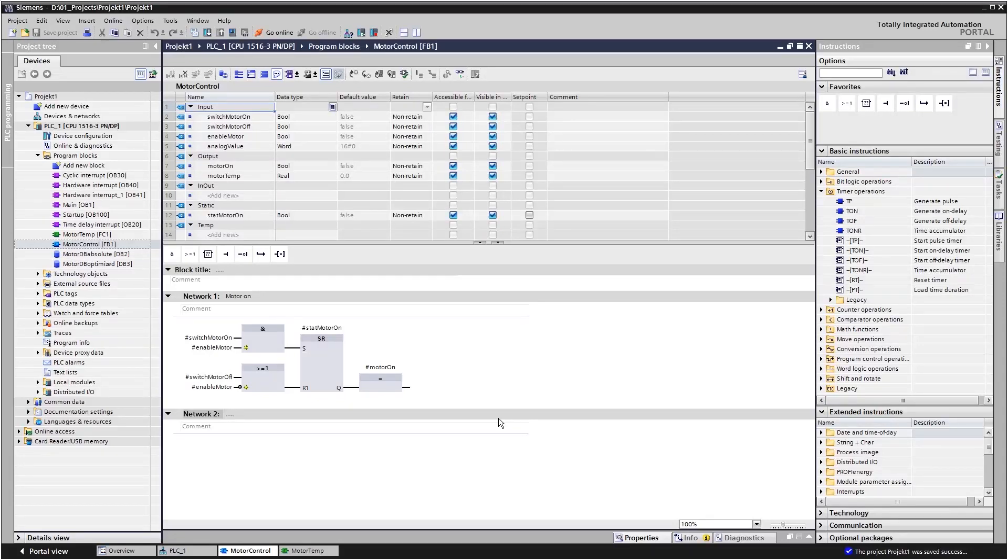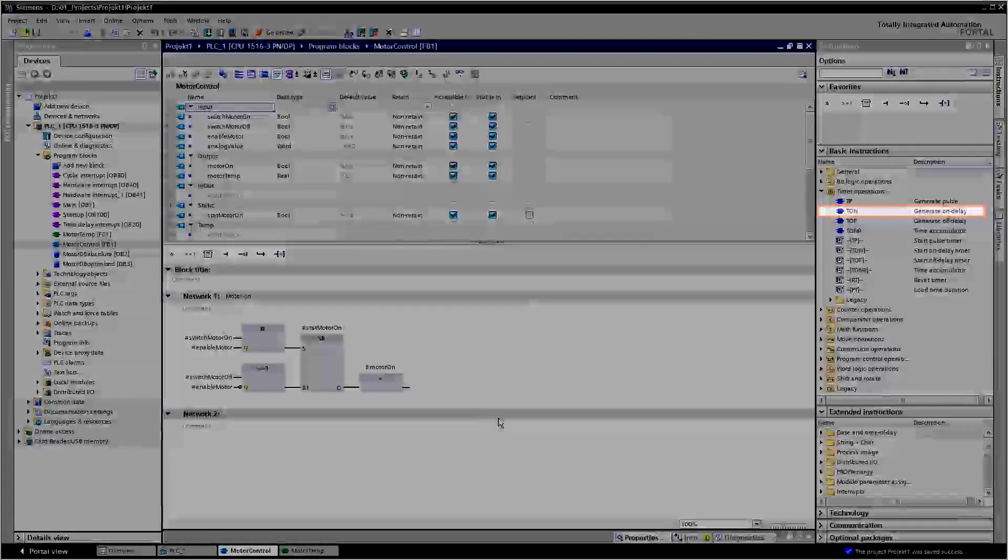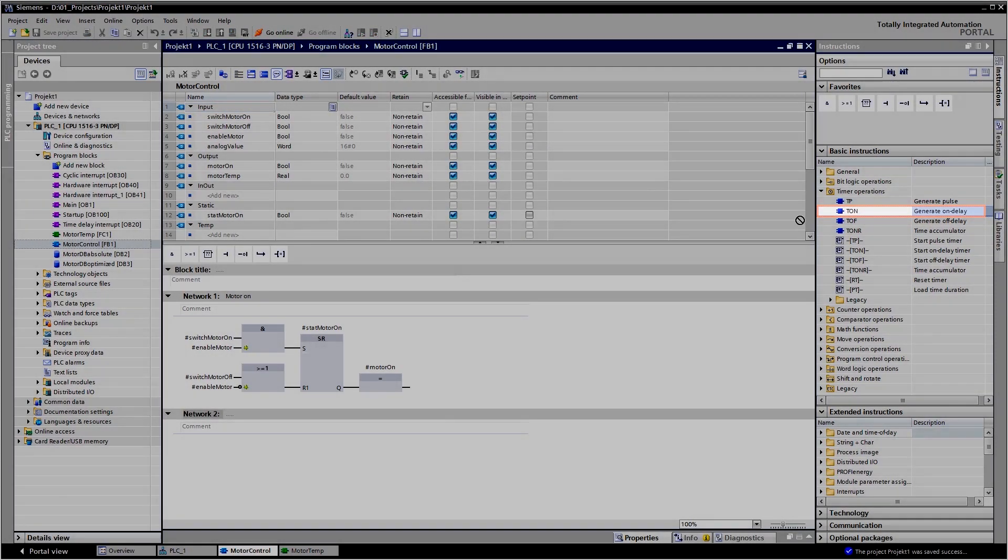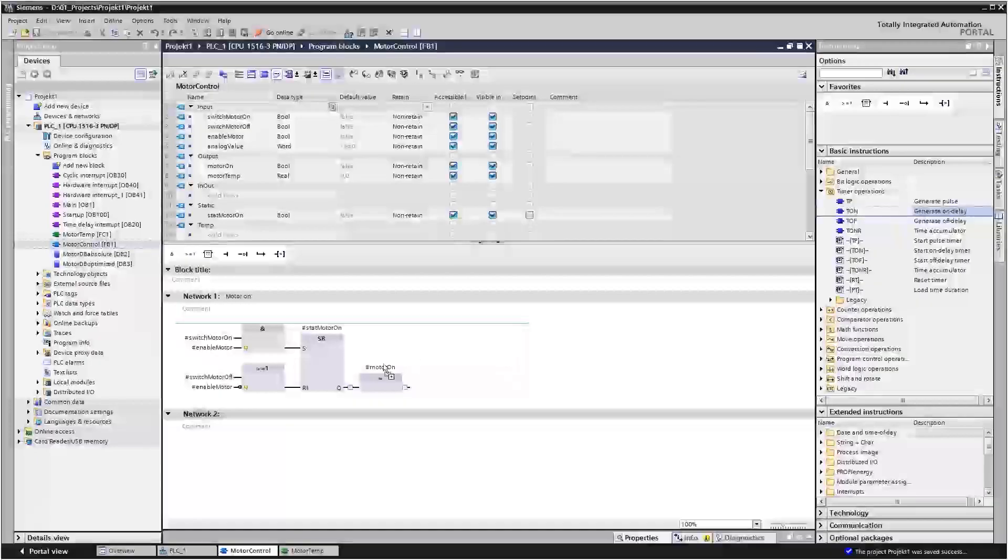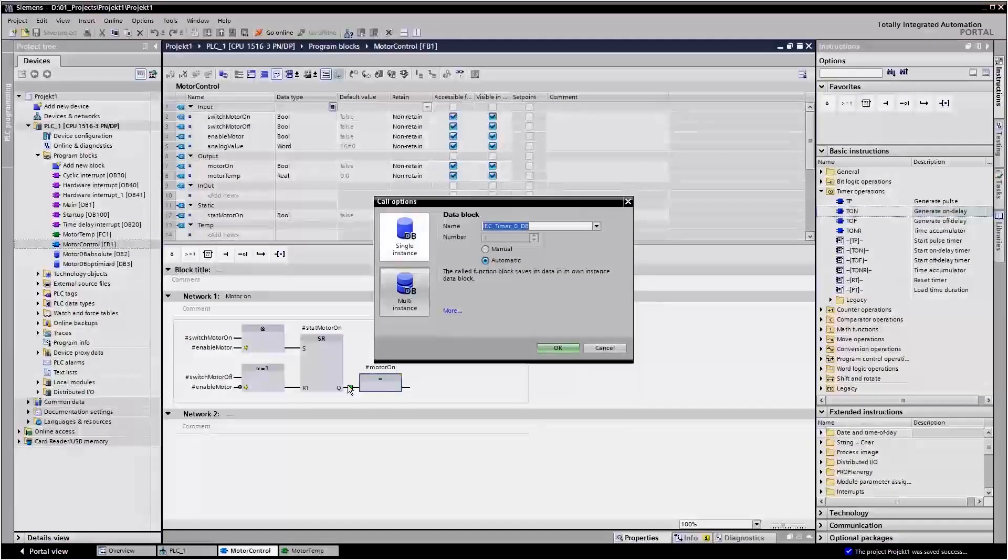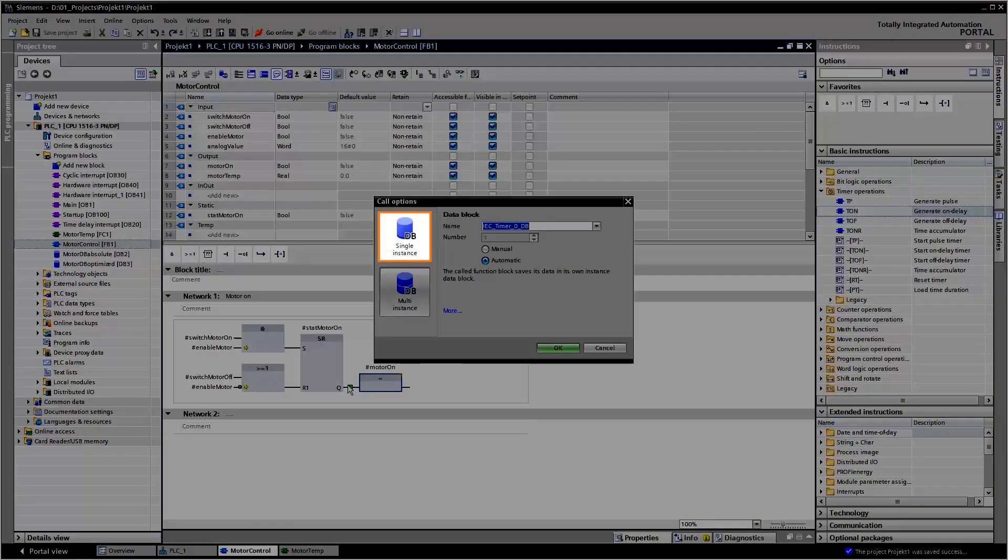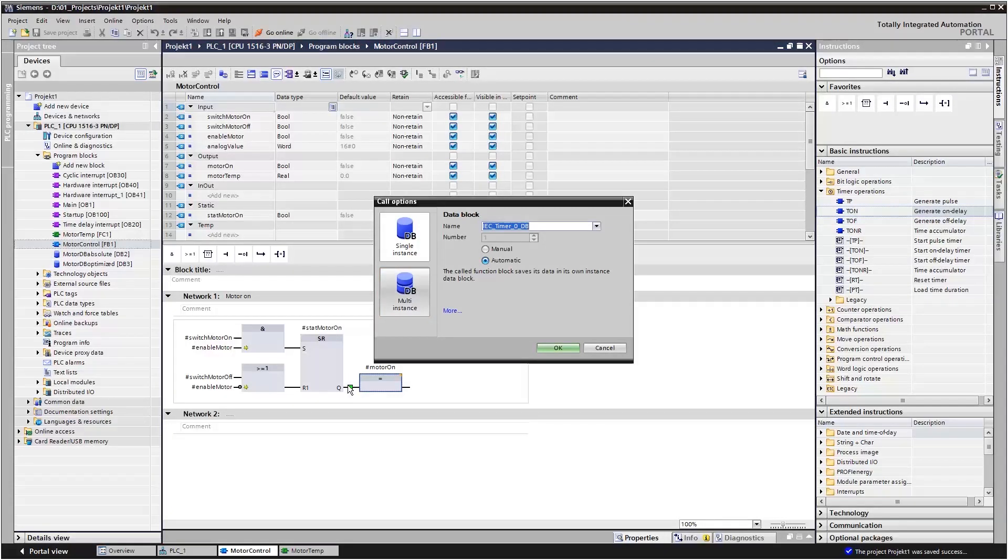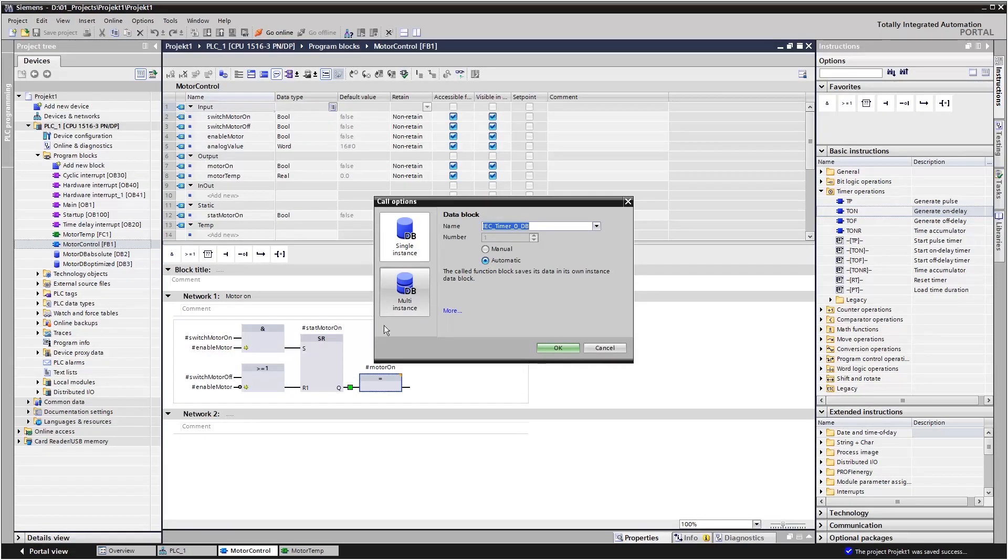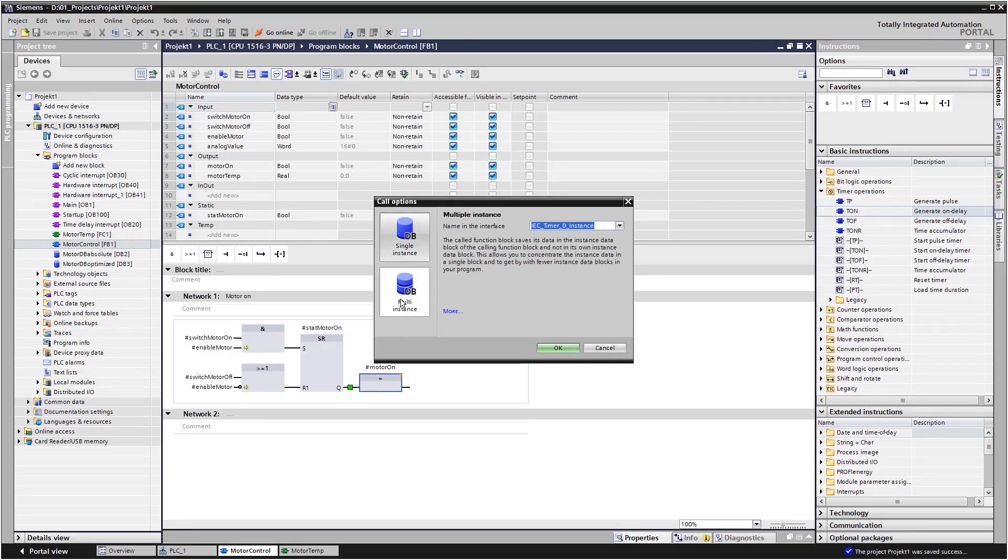Let's say you want a delayed motor start. That means you will have to call up the command on delay in the function block. You can choose between single instance and multi-instance for call-ups. A single instance command will receive its own instance data block to store the tags.